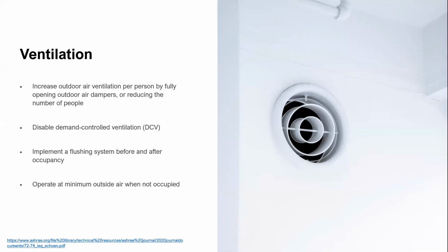Next is operate at minimum outside air when not occupied. You can talk with your building engineers and your property managers, especially for offices that are renting, so that they can open their ventilation system overnight, so that you would have total air exchange when you get back to the office the next day.